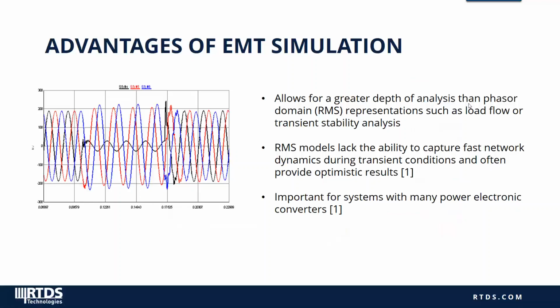So why EMT simulation? Well, for steady state analysis, phasor or RMS solutions certainly provide satisfactory results, and traditionally they've been the most widely used type of model from a power systems planning and operations perspective. That being said, there is a lack of ability to capture subcycle phenomena associated with transients, and also the ability to represent low-level controls of inverter-based systems. We've seen increasing evidence that, particularly in systems with a high penetration of converter-connected generation, phasor simulation provides optimistic results. EMT simulation might be preferable or necessary in these situations, as it's more likely to provide realistic results and predict things like control instability reliably.